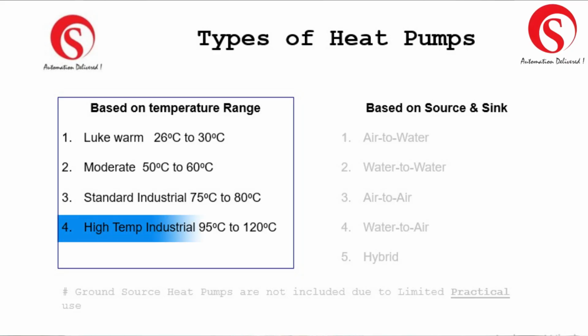The latest addition in the heat pump category using refrigeration equipment is the 120 degree centigrade heat pump. All of you are familiar, you might have seen 180 degrees, 240 degrees and all kinds of temperatures using high pressure boilers or thermic fluid heating systems, or heat recovery systems, assuming you have an aluminum foundry or something, where you recover heat from the flue gas. You might have seen all higher temperatures. What I am talking about today in this episode is whatever we are able to generate using a simple refrigeration system, in the smaller capacity range.